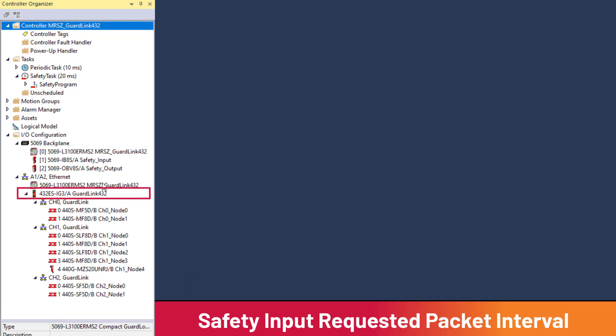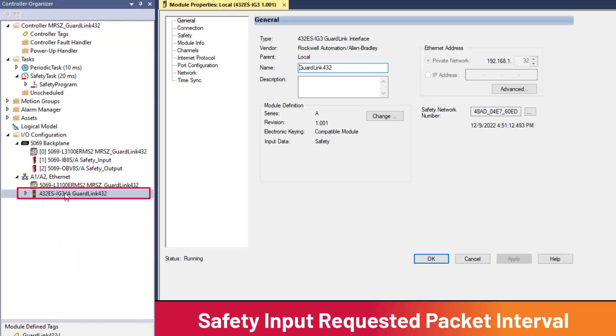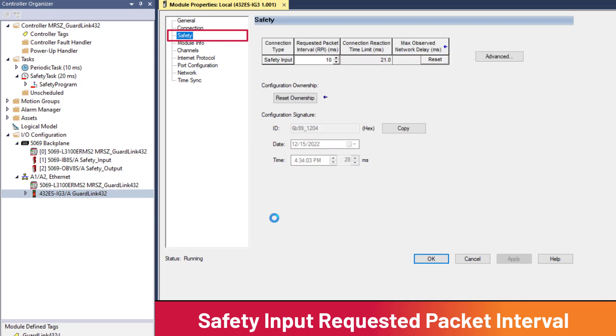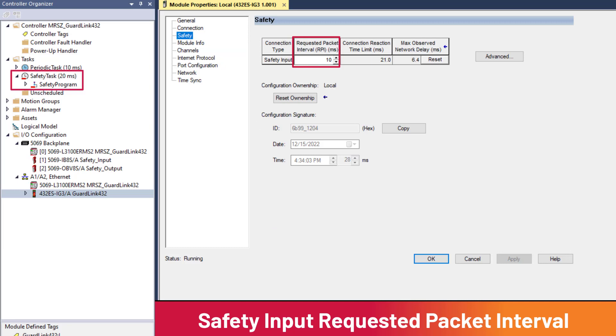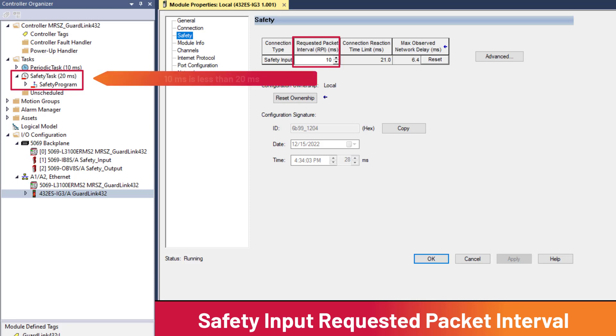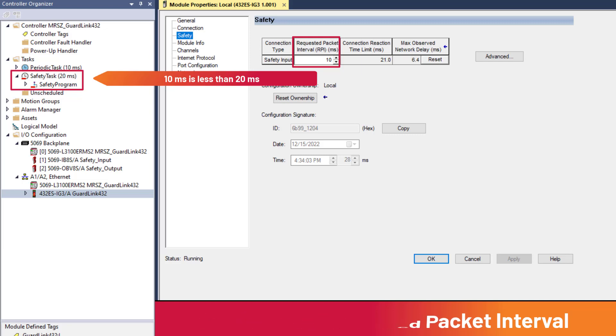Let's verify that the input RPI has been set to provide the safety task fresh data each scan. In the I/O configuration, double-click the 432ES-IG3 and go to the Safety menu. The request packet interval is set to 10 milliseconds. The periodic safety task is configured to run every 20 milliseconds, as shown by the value in the brackets next to the safety task. The RPI and safety task period are coordinated to provide fresh data each scan of the safety task.